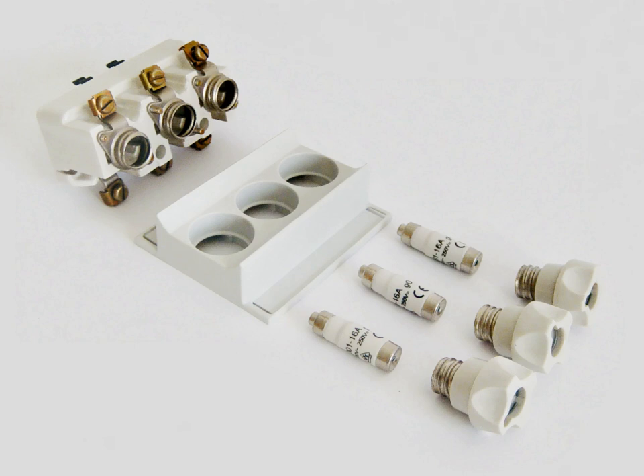Topic. D0 system, NEOZED. Fuses of the D0 system, read as D zero or NEOZED, are smaller than the DIAZED fuses. NEOZED fuses are divided into three sizes. The D03 size is used very rarely, because with these high currents NH fuses have proven to be more reliable. In circuits with a very high prospective short circuit current level, more than 50 kA, D fuses cannot be used and type NH fuses are used instead.